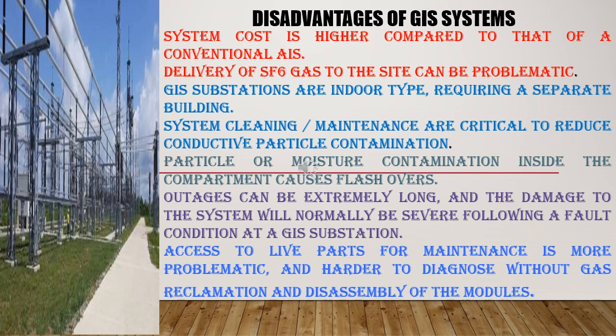Disadvantages of GIS systems. One, system cost is higher compared to that of a conventional AIS. Two, delivery of SF6 gas to the site can be problematic. Three, GIS substations are indoor type, requiring a separate building. Four, maintenance is critical to reduce conductive particle contamination. Five, particle or moisture contamination inside the compartment causes flashovers. Six, outages can be extremely long, and the damage to the system will normally be severe following a fault condition at a GIS. Seven, access to live parts for maintenance is more problematic and harder to diagnose without gas reclamation and disassembly of the modules.